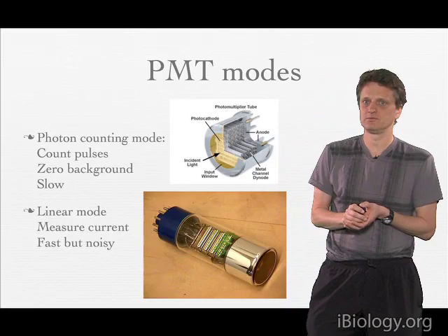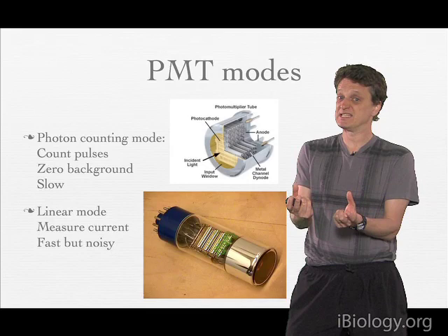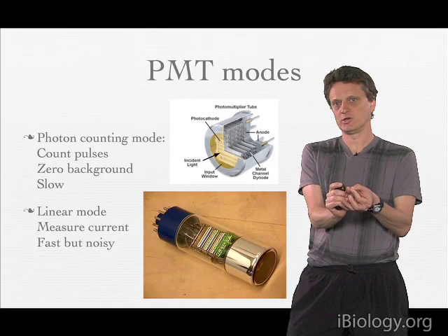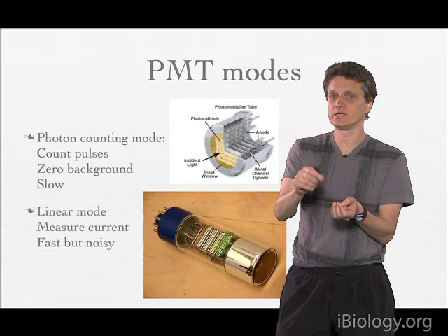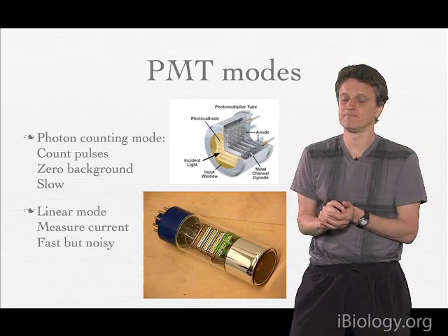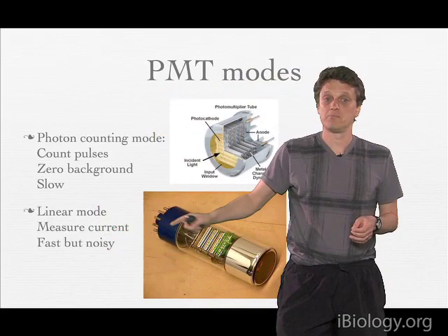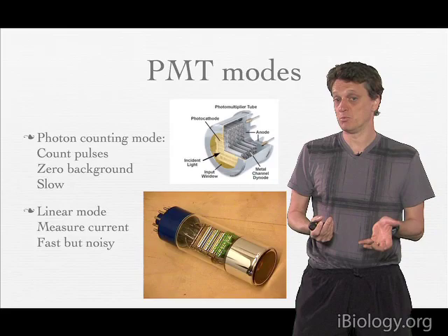A nice example of the photon counting mode is what you see in Geiger counters. Geiger counters are basically a PMT with a scintillation material in front of it, so that radioactive material is changed into a photon. That photon hits the photocathode and with every hit you get a count, which you can hear in your Geiger counter. The other mode is the linear mode, where we measure the current, which is a much faster mode of operation but also has more noise.